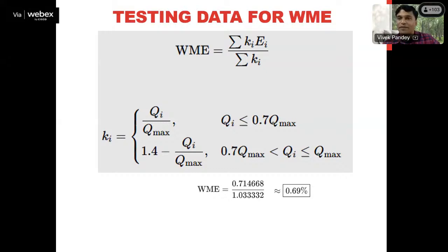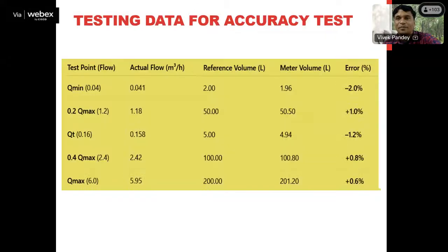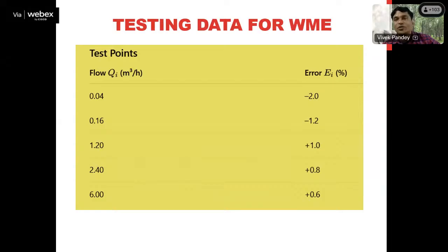In the accuracy test I have shown you, 5 errors are calculated: minus 2%, plus 1%, minus 1.2%, and so on. So these are basically E1, E2, E3, E4 and E5. These are the E values, and the K values you can calculate using the flow rates which are specified. You can see here that we have selected Q1, Q2, Q3 like this, and the last value is 6 meter cube per hour, and the corresponding errors are also given.